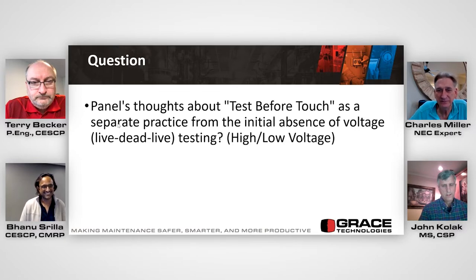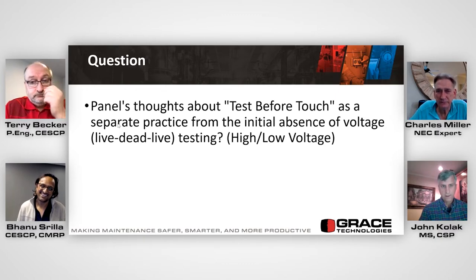Well, just the caveat about high voltage is that if you have a high voltage system, you've got to get a visible open and install a full set of personal protective grounds. If you've done that, and they're equipotentially bonded, then you don't need to test before you touch because you're sure it's out of service then. So on the high voltage side, it's a moot point. We know the answer to that. If you've got a full set of grounds on, you don't worry about it.